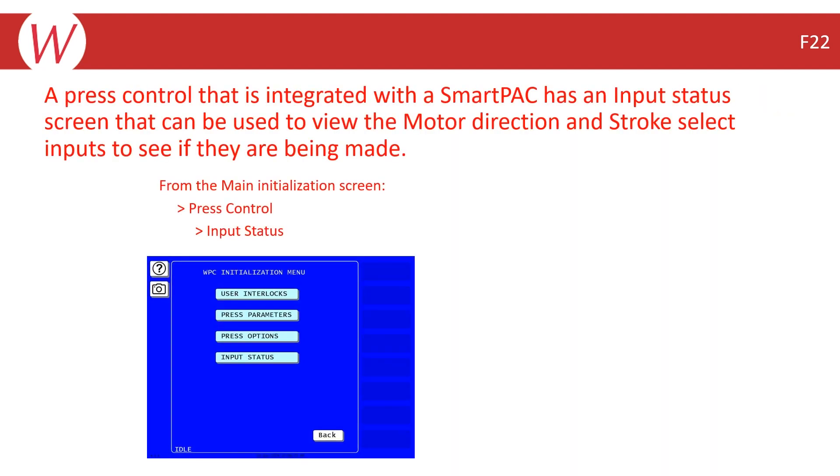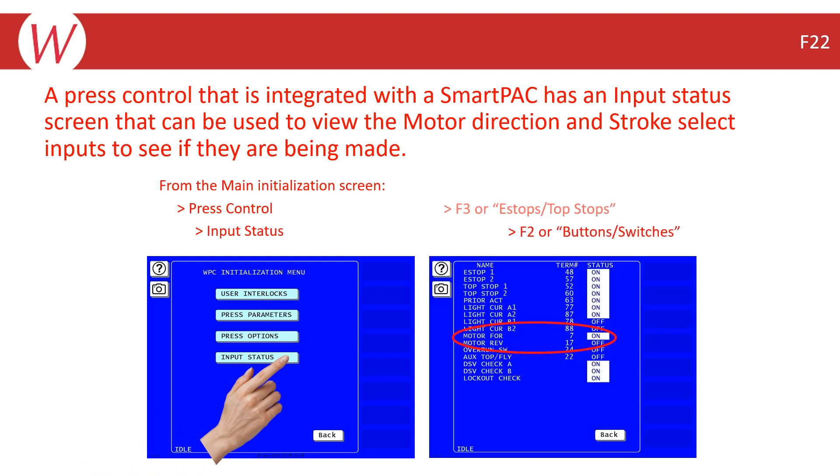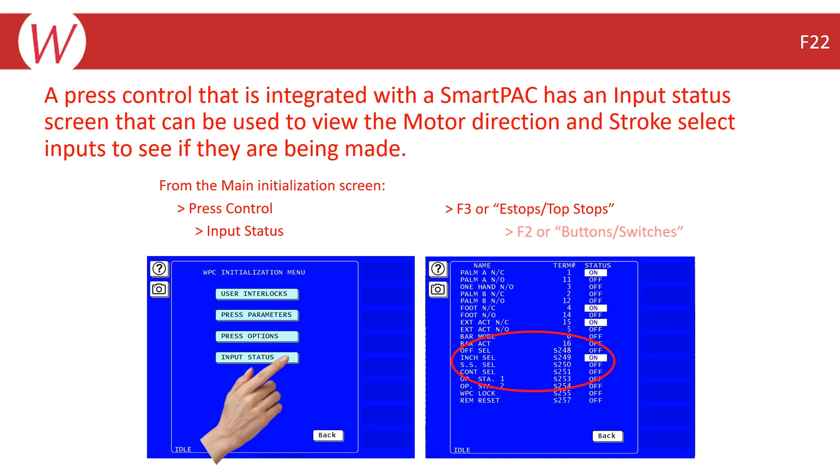If you have a press control that is integrated with a SmartPAC, you can view the status of your motor forward and reverse, as well as the stroke select inputs, from the input status screen in the main initialization menu. From the main initialization screen, select press control, then select input status. Select F3 or E-stop/top stops to view the motor direction inputs. Then press back and select F2 or button/switches to view the stroke select switch inputs. On means they are being made, and off means they are not satisfied.